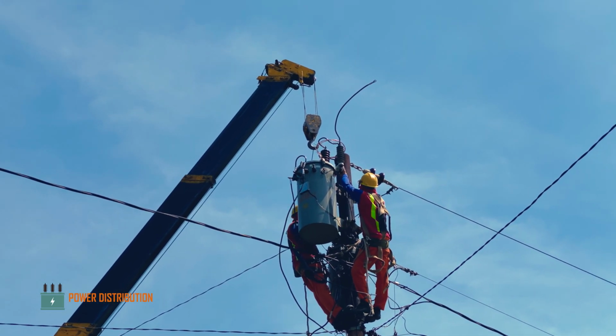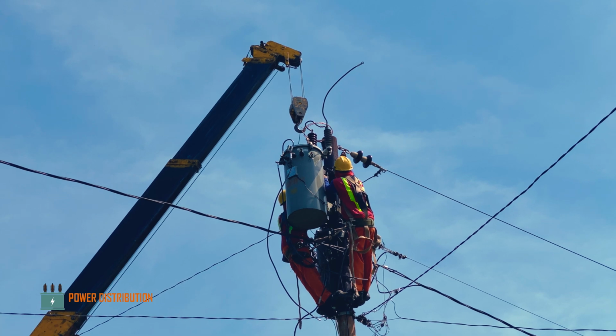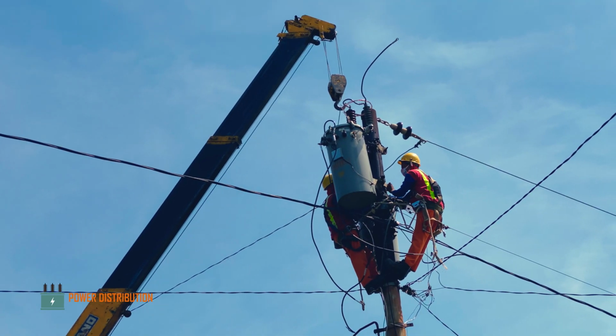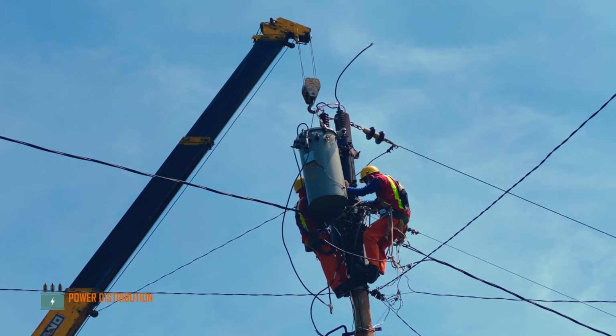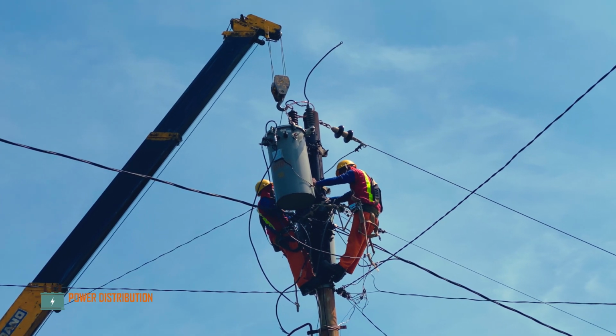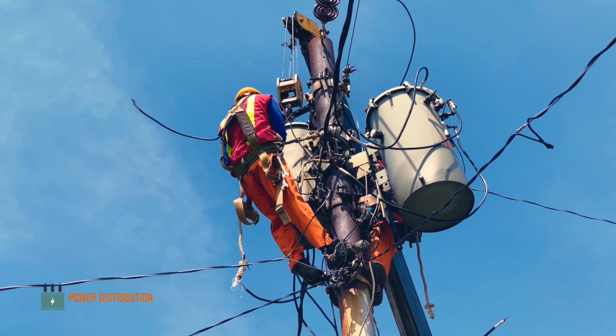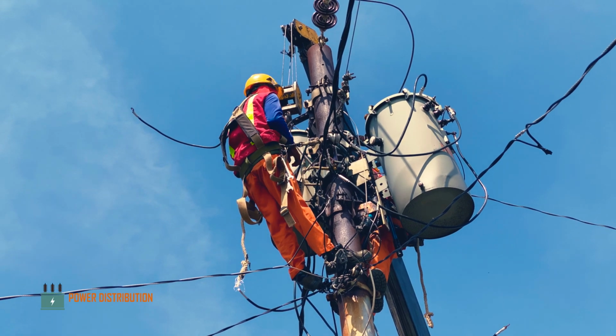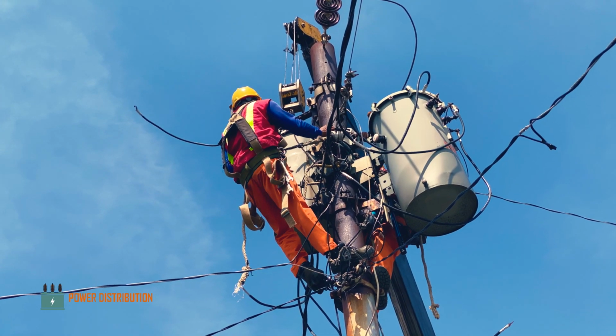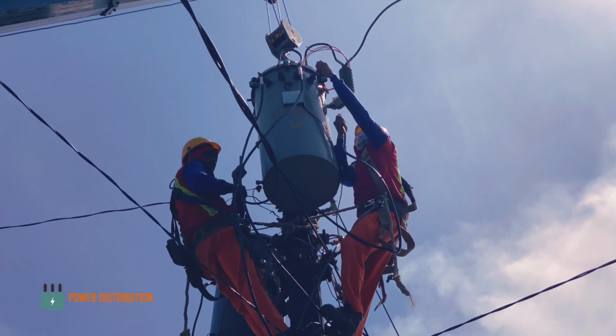FYI, this transformer is hermetic type, meaning that it doesn't have any conservator tank or breather. Completely sealed from atmospheric pressure, so it doesn't need any maintenance whatsoever, which is suitable for harsh climatic conditions like Indonesia.